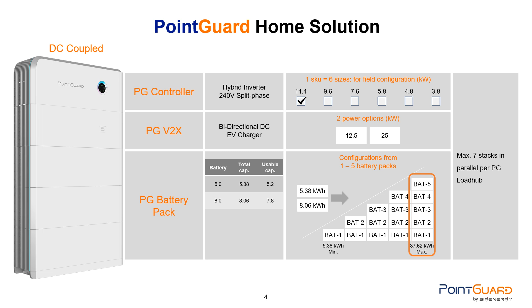We can parallel up to 7 stacks in a single PointGuard load hub. The PointGuard load hub is our backup and load control panel. At the top, you have 5 double pole or 10 single pole controllable breaker slots that are controllable and monitored through relays and CTs independently of each other.